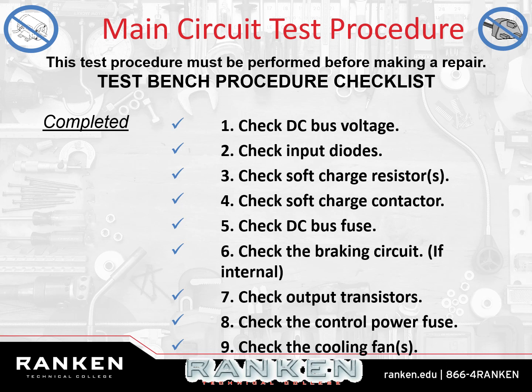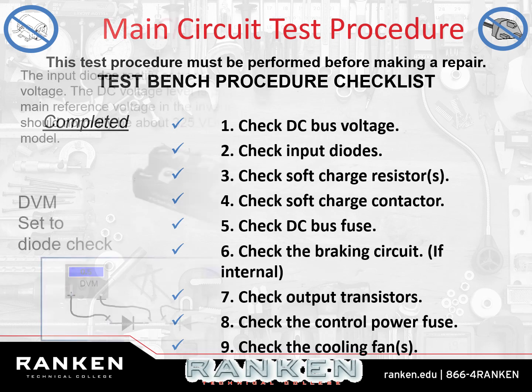I could have already had a new drive put in, and we're back running in the time it takes you to just take the drive completely out and check it. And then are you going to be able to fix it once you've checked it? Probably not. That's why we just say if it's less than 100 horsepower drive, throw it in the trash.